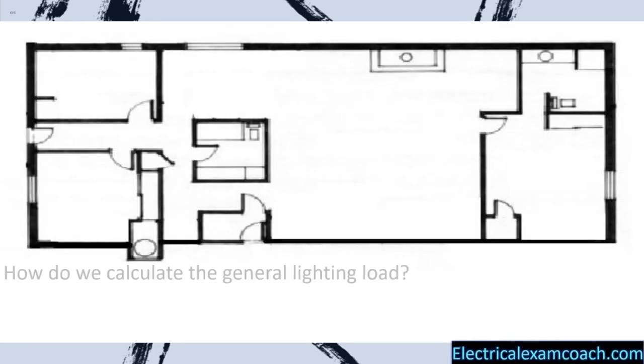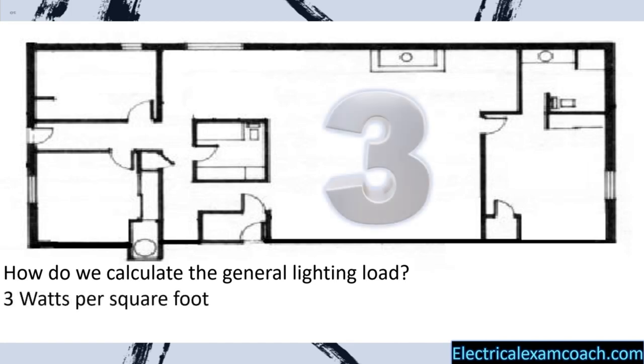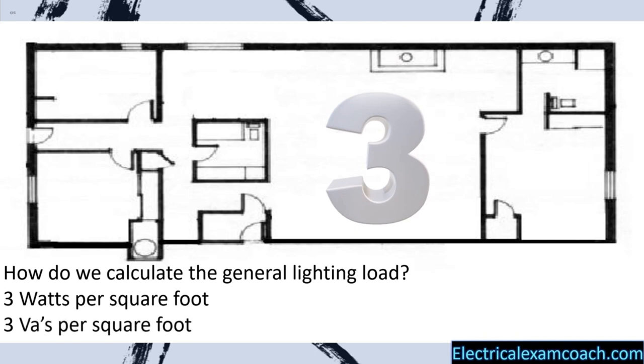The first question we have to ask is how do we calculate the general lighting load? We're not going to calculate it per receptacle or per light fixture — thankfully, they've made it very simple. We're going to calculate it at 3 watts per square foot. For all general lighting and all general receptacles, all we have to do is take the square footage of the dwelling unit and multiply it by 3. The code language actually uses VAs, so 3 VAs per square foot.